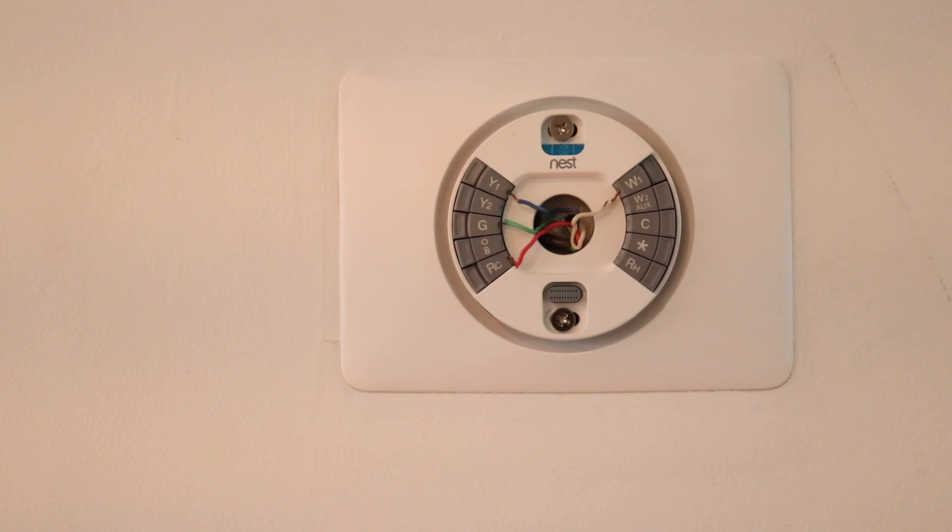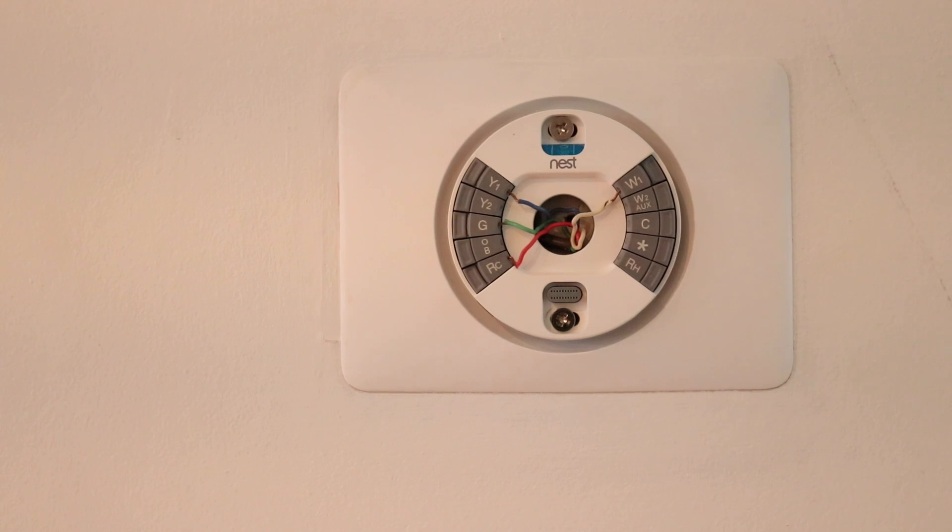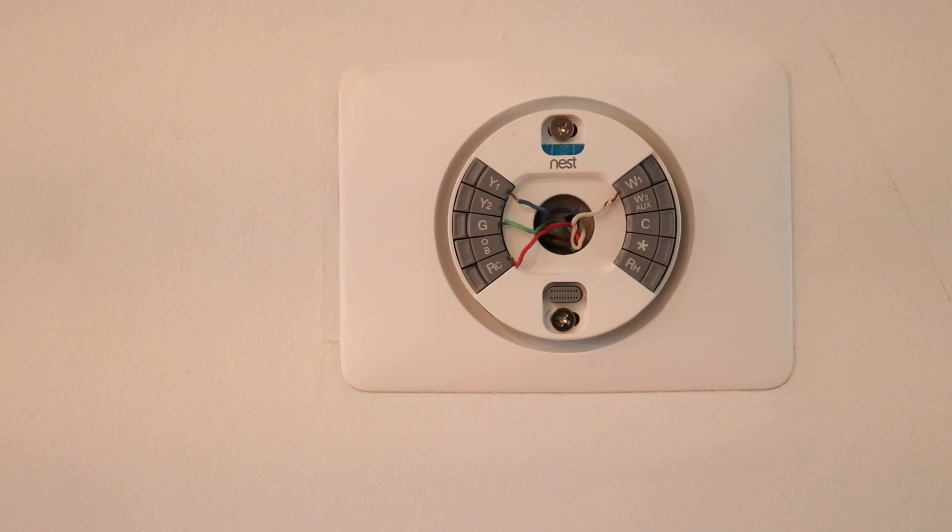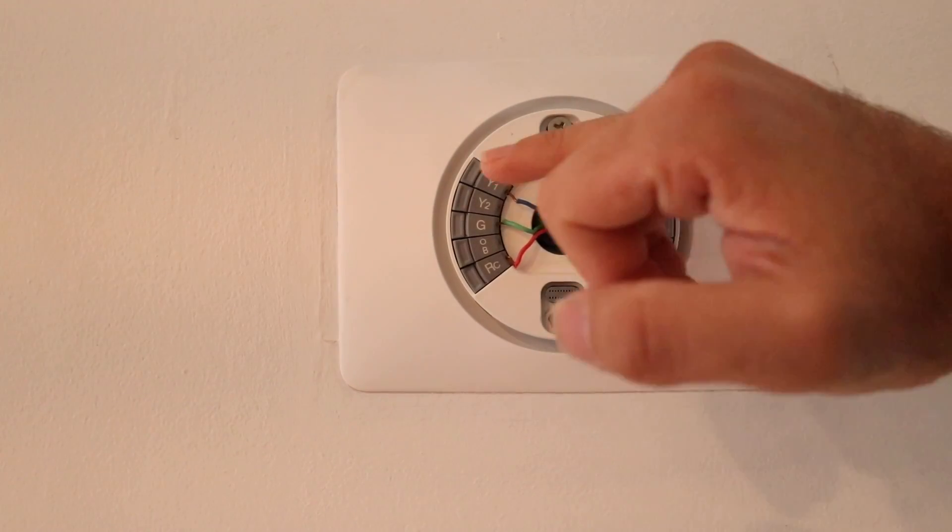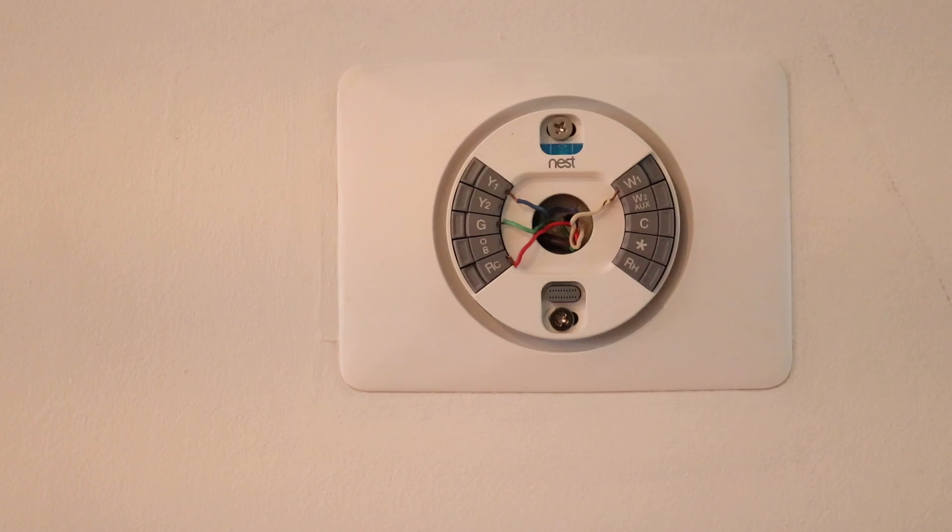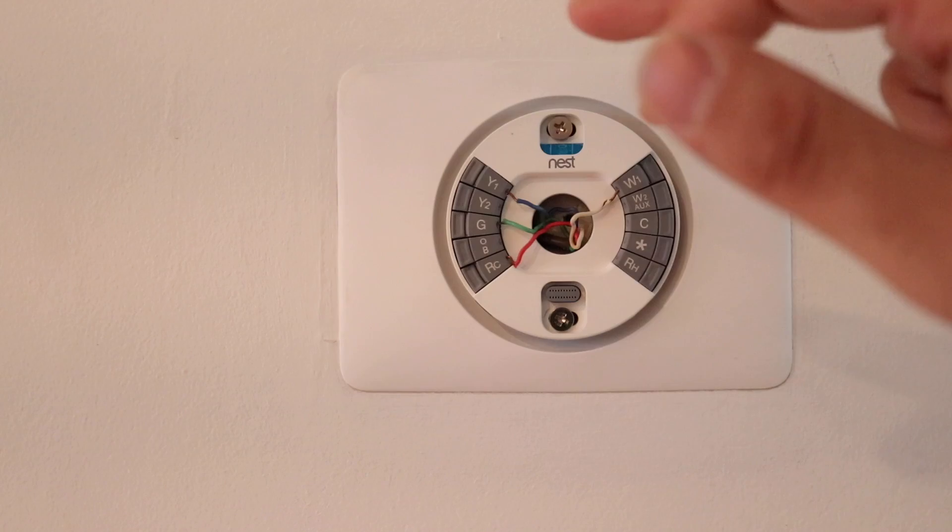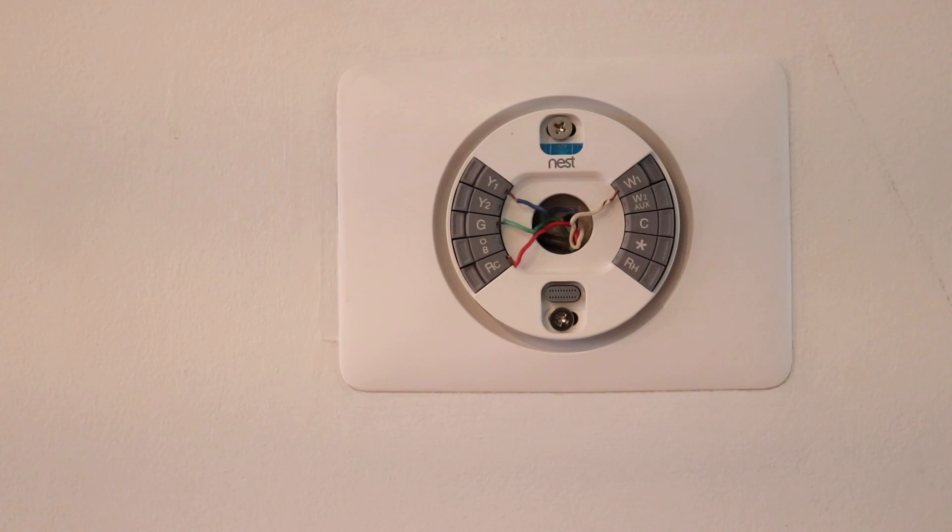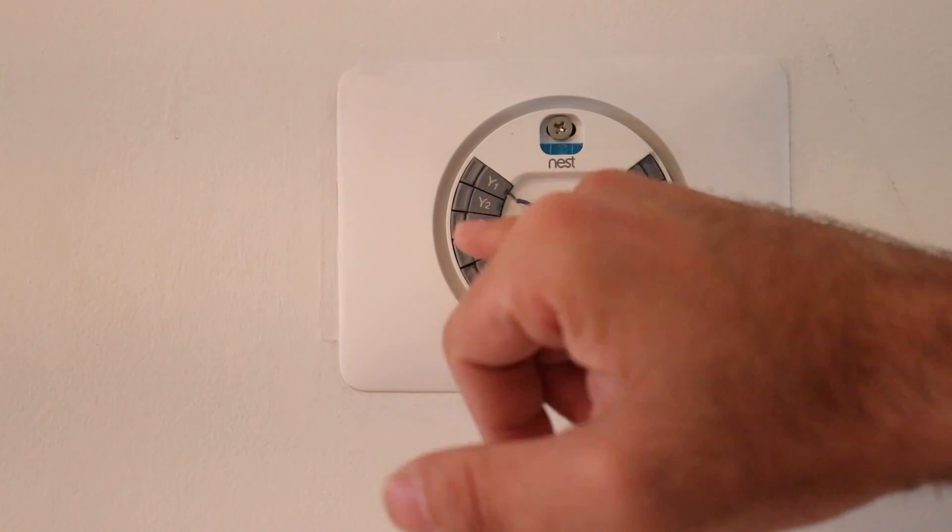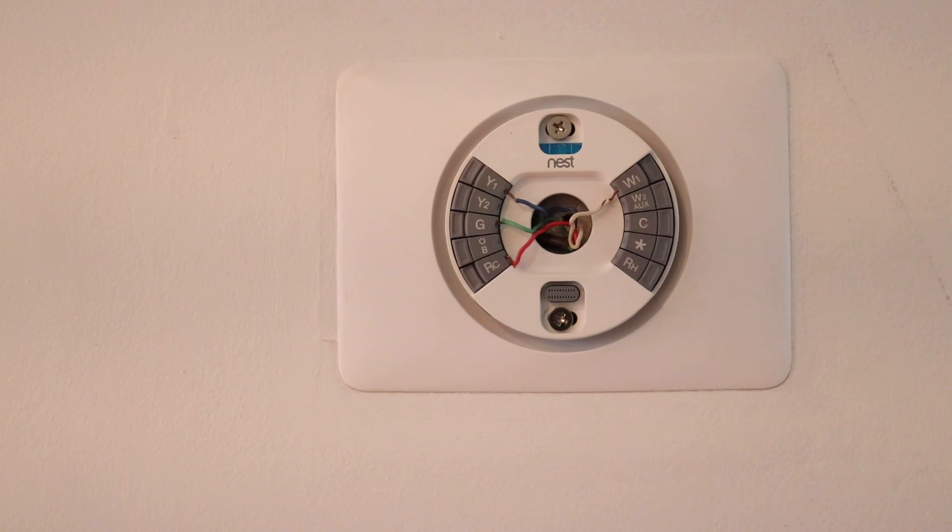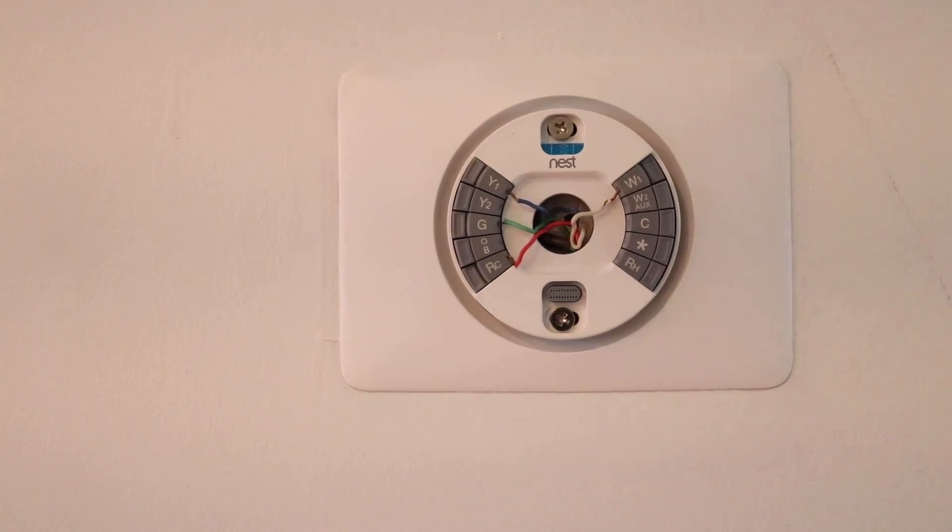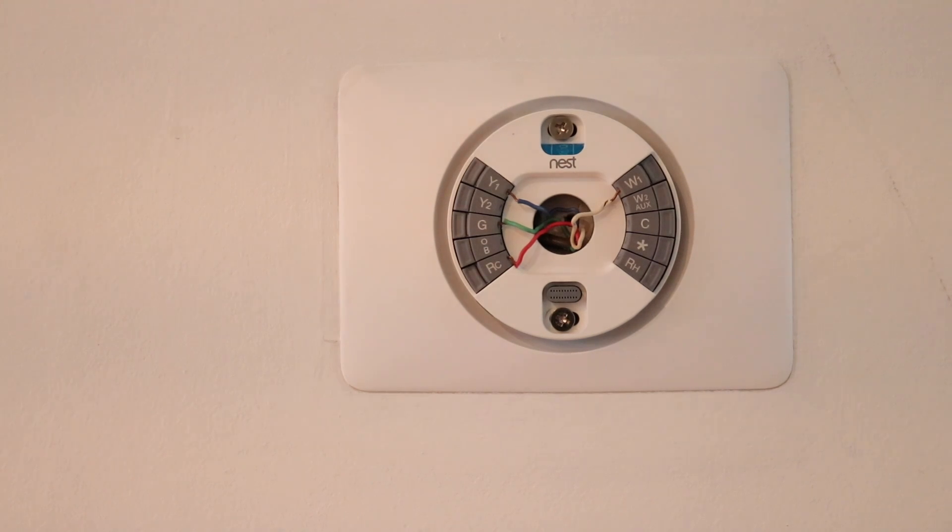The G wire, all that does is power the blower motor, the fan motor, to blow air throughout your house independently of heating and cooling. When you have heating or cooling, air conditioning or heat called for, the fan motor will automatically go on even if you don't have the G wire connected. That is how modern HVAC systems are built. The only purpose of the G wire is if you wanted to control your fan independently to circulate air throughout your house without providing heating or cooling.